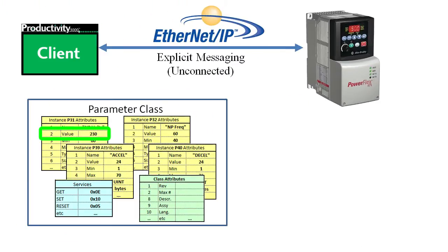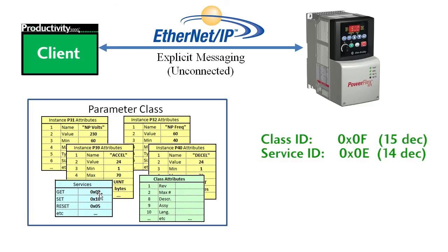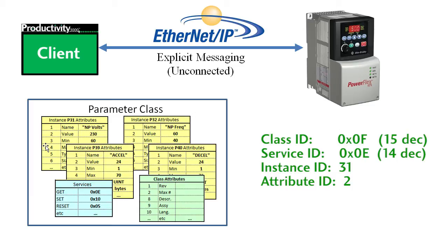Suppose we want to get the value of parameter 31. We look up the manual and find that the parameter class is number 15 (0x0F hex), the get service code is 0x0E, the instance of this object we want is number 31, and the attribute we want is number 2 — the value. We simply hand those numbers to the explicit message instruction and it fetches the value of that parameter for us.